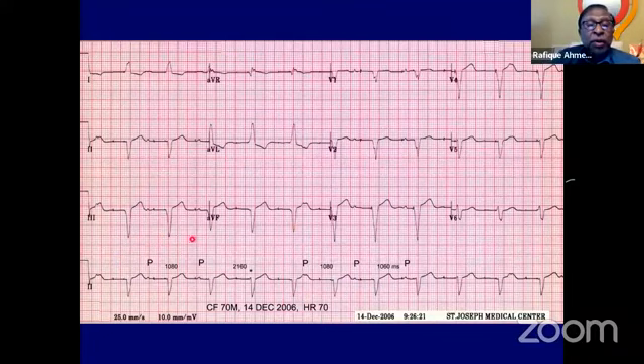And you have to make sure that you identify this rhythm, because with this pacemaker there are a couple of possibilities. You can have sensing failure because you did not program it right. You can have capture failure because you have a high threshold. Let's say the threshold is 2.7 and you programmed it 2.5. But it is very difficult for me to believe that the two things can happen at the same time. And this lead must have dislodged.